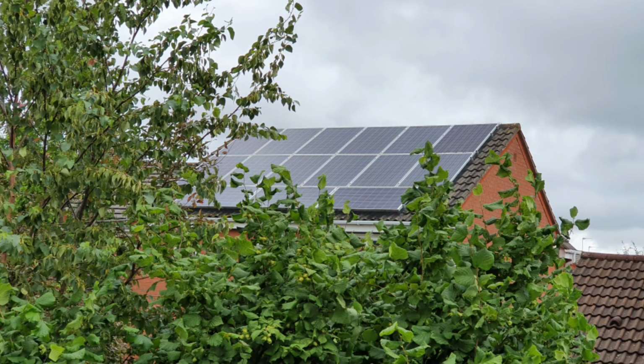For example, on a brand new housing estate, the first houses that are built and connected to a new transformer may have a slightly higher voltage than usual. Then a small natural fluctuation will be seen as a PEN fault, and for many products on the market, they'll disconnect the charger. Another example of where this could happen is if there's a high presence of renewable energy sources locally, such as banks of solar PVs or wind turbines, either on the property or close to it.